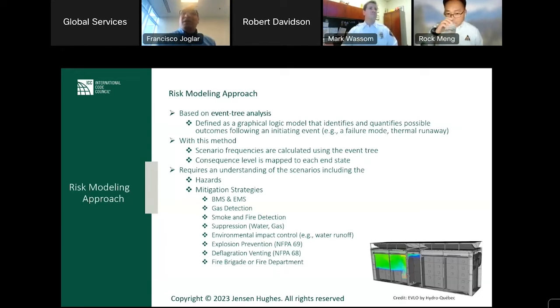We already talked about the management system to monitor the well-being of the battery. That is the key preventive measure for thermal runaway. Some of these cabinets are equipped with gas detection to monitor if there is hydrogen release and buildup of an explosive mixture. And if that happens, we may start a ventilation system, explosion prevention, to vent the gases and just prevent the explosion itself. Then some of them are equipped with fire detection, and they would catch smoke and release, in some cases, a gas suppression. So you can now see the logic involved.